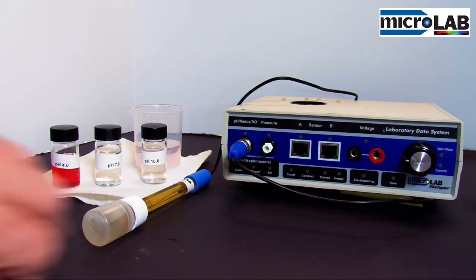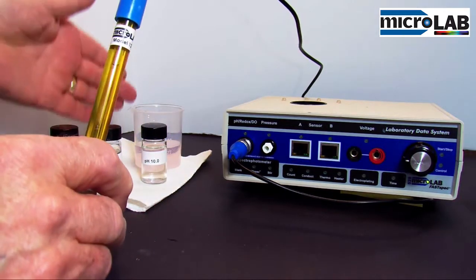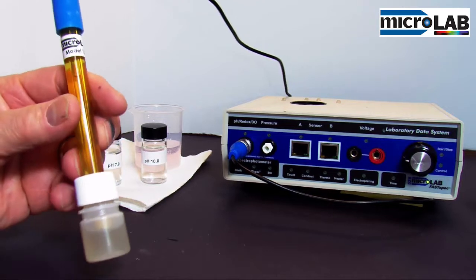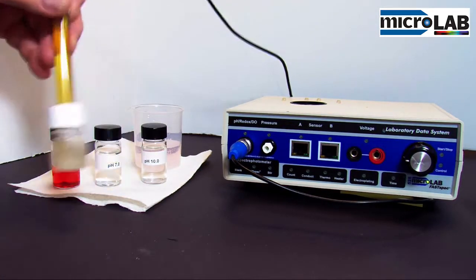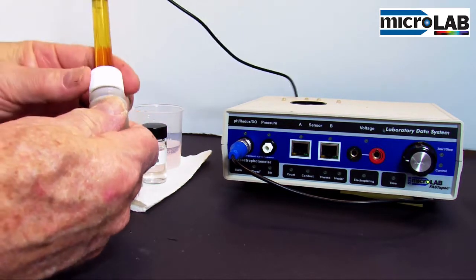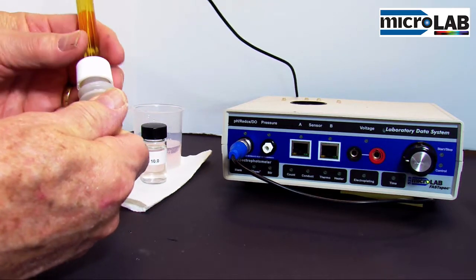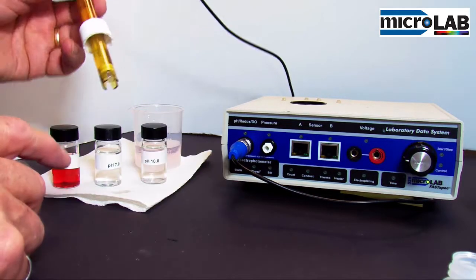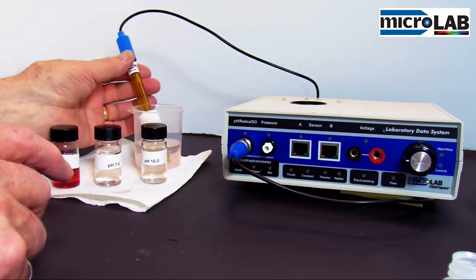And I've got a pH electrode. I've got a beaker of water back here to rinse the electrode between measurements. And I've got 3 buffers. The pH electrode has a little vial on the bottom that contains a buffer, a constant pH solution. I'm going to put it in the water just to hold it for a minute here.